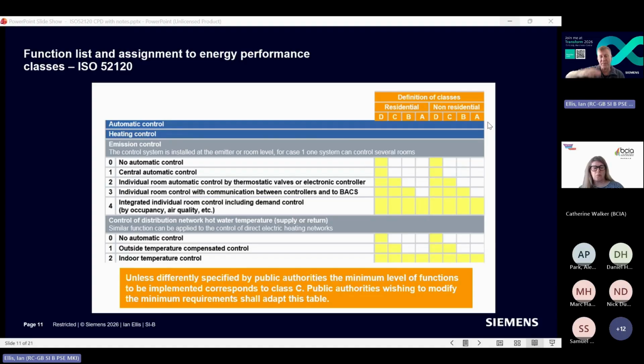But then the next one down says, well, I can go a bit further. So to get to class B, I have the individual room control again, but I have some sort of feedback or communication between the controllers in the individual rooms or spaces back to my BMS system. So then I can say, well, I've got 10 rooms that I'm feeding from this boiler, but at the moment only 3 of them actually have a requirement for heat. The BMS can then make a decision to either turn down the boiler set point or turn it off. So I've added another level of control, and I've gone up the scale towards B.